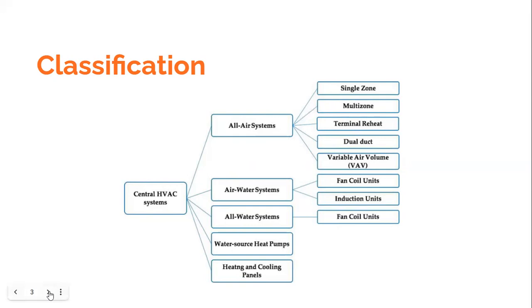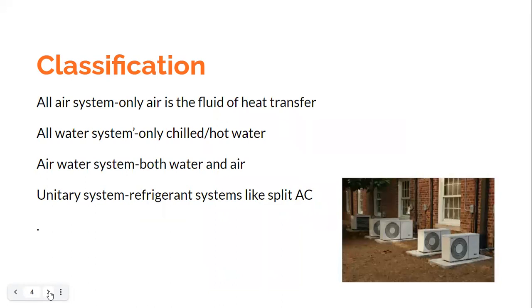Okay, so this is the broader classification of HVAC systems, and then it would be interesting to know which system to choose for a particular application. So as I said, all air systems would include only air as the fluid of heat transfer. In your all water system, only chilled water or hot water, or chilled and hot water are used for the heat transfer for achieving the conditioning effect. And in your air water systems, you use both the water as well as the air for getting the conditioning, right? In unitary systems, as I had mentioned, you would have only refrigerant which is flowing through the piping and achieving the conditioning effect. Okay.